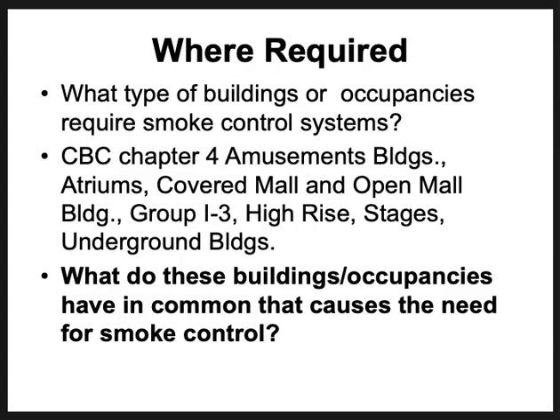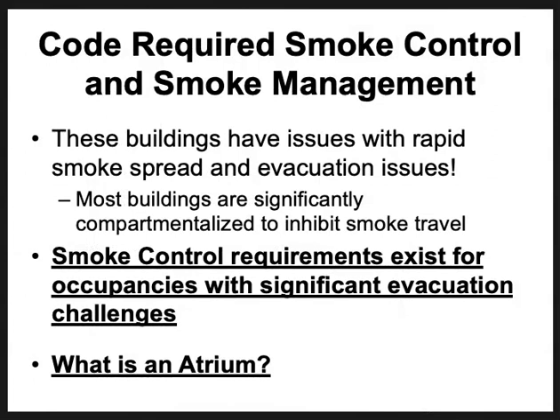Well, the California Building Code has a whole chapter on it. Chapter 4 tells us that amusement buildings, atriums, covered malls, open malls, I-3s, high rises, stages, underground buildings, these types of facilities, they need smoke protection. So what do these buildings all have in common that causes the need for smoke control? Well, two very important things. These buildings have issues with rapid smoke spread most of the time because they have atriums or open floors or openings that go from floor to floor. And the other thing they all have in common is evacuation challenges.